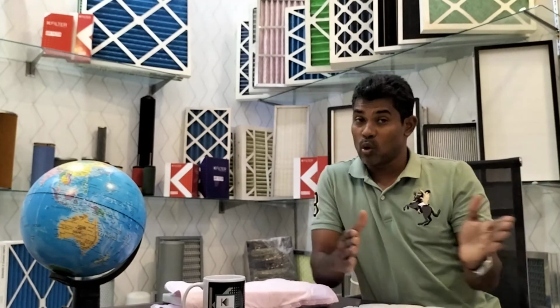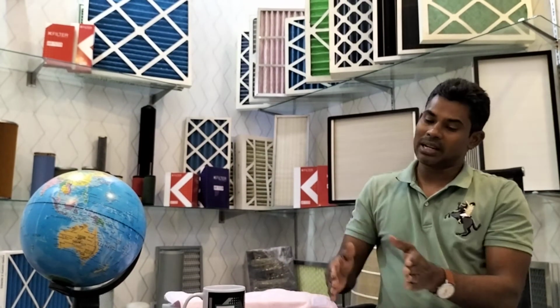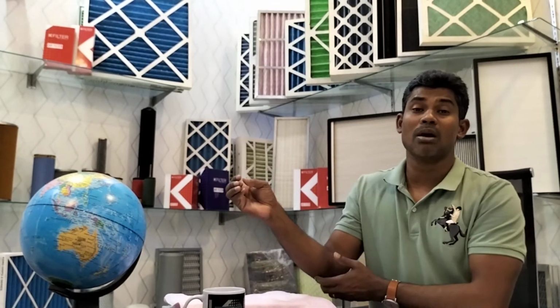So if you are going for increasing the lifespan, for the changing period of the filters, you will change all of them, like pre-filter, fine dust filtration section and absolute filter. All of them will come with much more expense on your annual maintenance contract. Maybe you are changing yearly, or every 6 months, so you will change all of them. The better solution is to change the pre-filters and pocket filters periodically. Then you can save on the absolute section. You can always keep it. Absolute filters, maybe 2 years or 1.5 years, you need to replace.